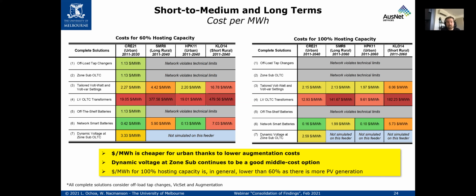Finally, the dynamic voltage target at the zone sub is that great middle ground, even per megawatt hour. You might worry that a stricter inverter setting impacts curtailment — it does marginally increase curtailment, but not by much, and that's reflected in the dollar per megawatt hour. If we had excessive curtailment, that cost would go right up, but we don't, so it's still a great option.